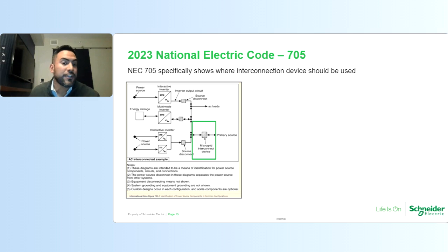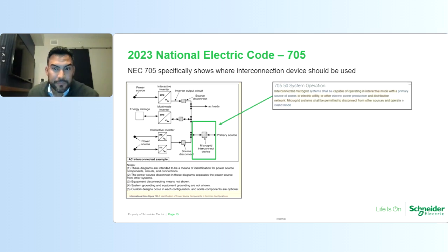The microgrid interconnection device is here. The purpose is to safely disconnect from the primary source. So this device is bidirectional. It's capable of operating in what the National Electric Code references as grid interactive mode with the primary source, and has the means to disconnect from other sources to operate that microgrid in island mode. So island mode is the resiliency of the system. If you want to use that microgrid for emergency power, it's the island mode feature in the microgrid interconnection device that will enable it to safely disconnect from the grid.